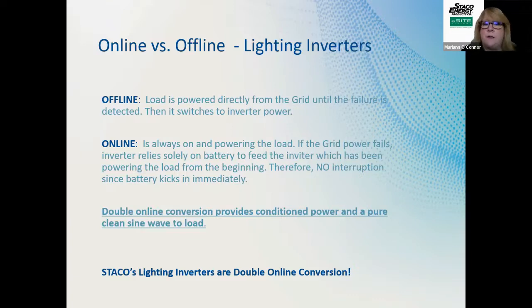With lighting inverters, there's online and offline. Offline is where the load is powered directly from the grid. So once a failure is detected, it switches over to the lighting inverter. The online is where the lighting inverter is always powering the load. So you have the power come in, it takes AC, converts it to DC. The DC charges the battery, goes from DC back to AC, and then you get a pure sine wave out to the load. So it's very conditioned, and the power is kind of cleaned up. So when power does go out, it's a very fast transfer. You don't have to wait for that inverter to come on because it's always on, because it's a double online conversion. So it kicks in immediately. And so the online lighting inverter definitely is an advantage as far as getting a pure sine wave out to your load, having power conditioned, and not having any lags when the power goes out and you need to switch over to battery. So next slide.